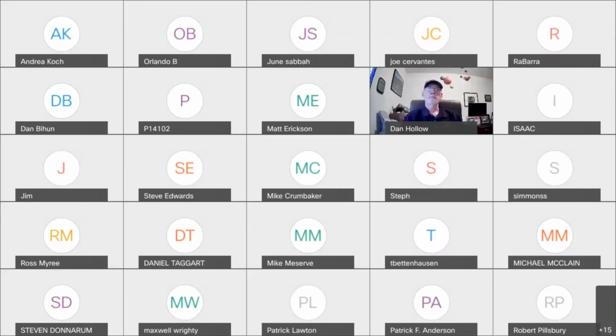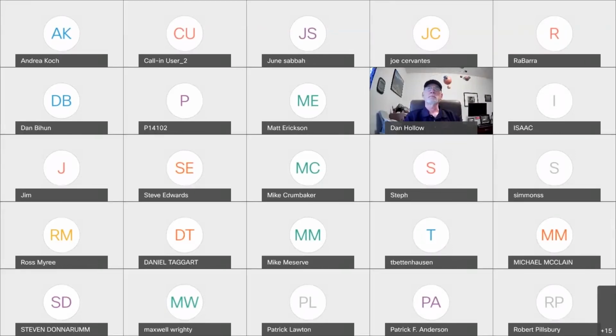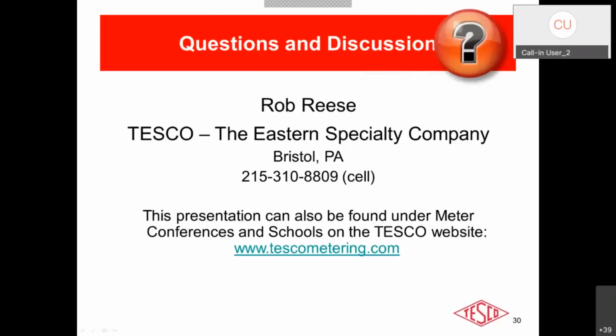Let's see here. How often should CTs be tested? The short answer to that is it depends on how much risk you're willing to assume. Like with all testing, like with meter accuracy testing, if you have a longer period between tests and you go back and do the next test and you find something wrong, if that's a longer period, then you have more time and more monthly bills to worry about, were they accurate or not. If you test more frequently, your risk goes down.